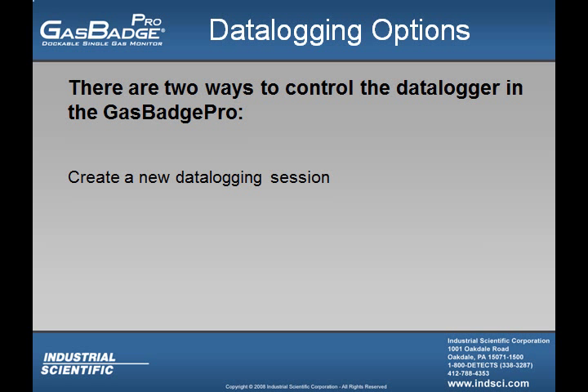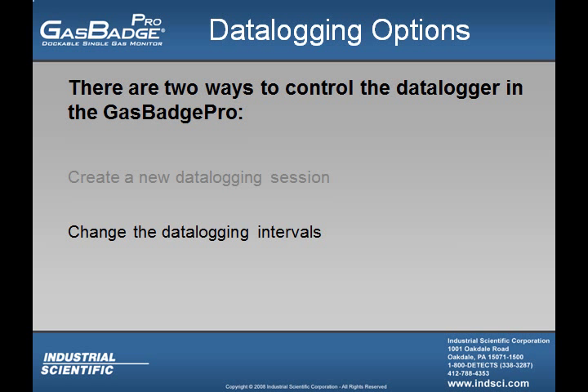There are two ways that allow the user to control the data logger within the instrument. The first option is to create a new data logging session. Data logging files can be broken down into sessions — a user may want to start a new session to keep data applied to a particular individual or a particular job. The second option the user is able to change is the data logging intervals, which can be set anywhere from 2 to 300 seconds.